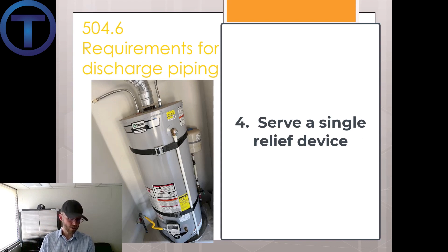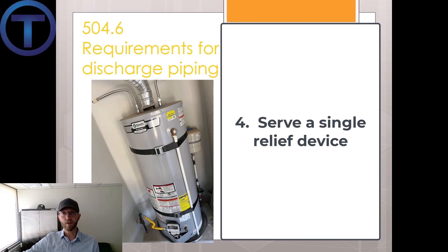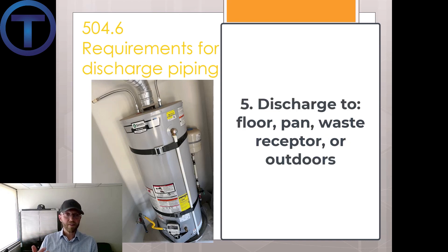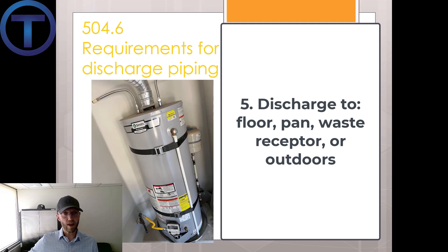Number four: serve a single relief device and shall not connect to piping serving any other relief device — we don't pipe these together from one water heater to another; each needs its own. Number five: it should discharge to the floor, to a pan, to a storage tank, to a waste receptor, or to the outdoors. That gives a variety of places to deliver that water to, but we need a place of disposal.